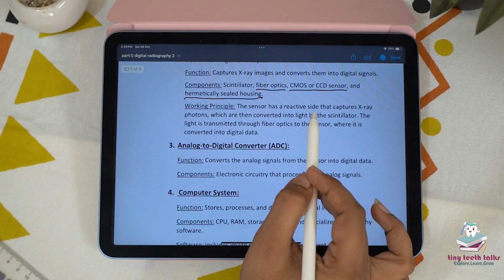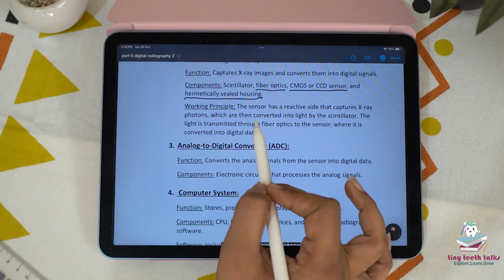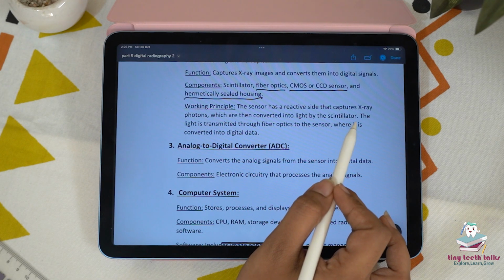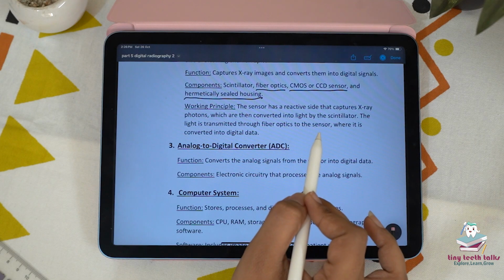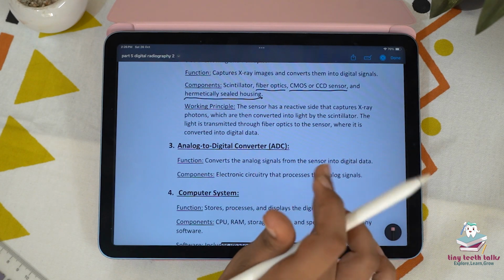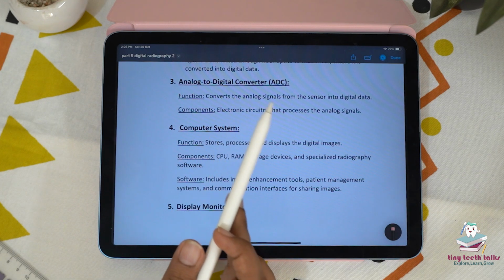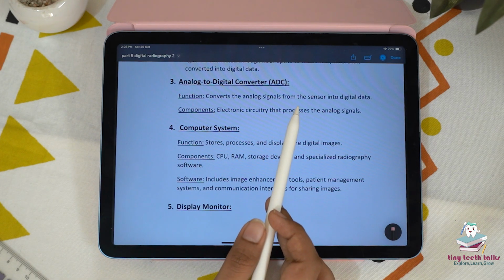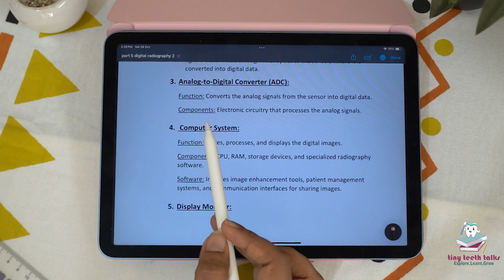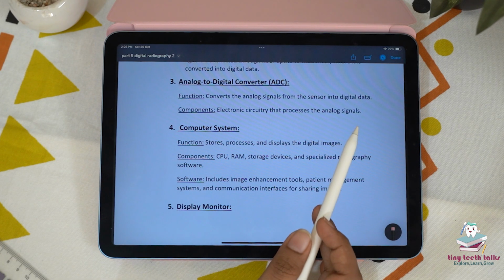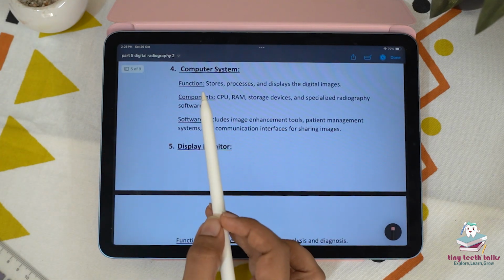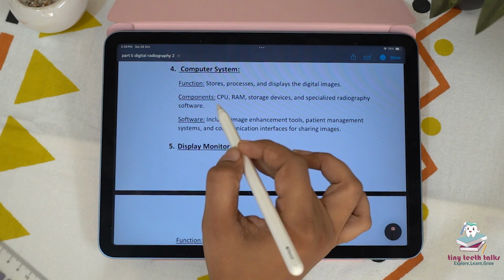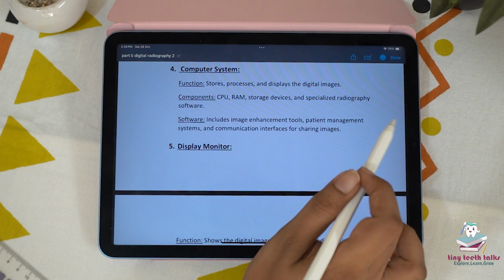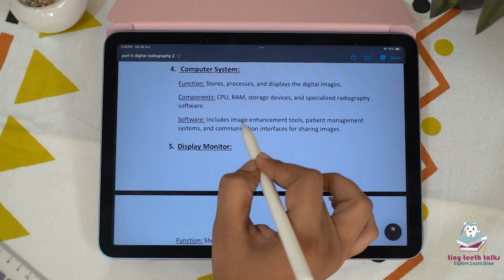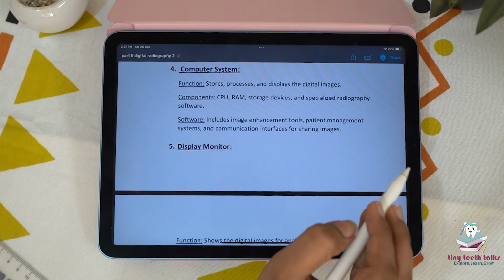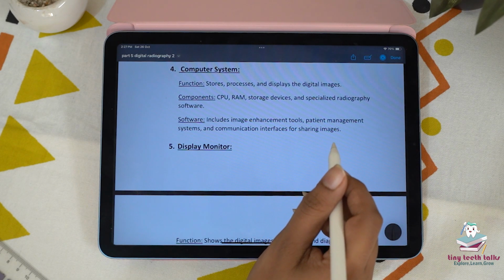So the sensor has a reactive side that captures the X-ray photons, which are then converted into light by the scintillator, and the light is transmitted through the fiber optics to the sensor, where it is converted into digital data. Now, the analog to digital converter converts the analog signals from the sensor into digital data. The components include an electronic circuit that processes the analog signals, then the computer system which stores, processes, and displays the digital images. CPU, RAM, storage devices, and specialized radiography software are the components. This software includes the image enhancement tool, patient management system, and communication interface for sharing images.